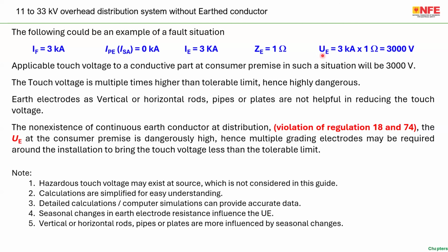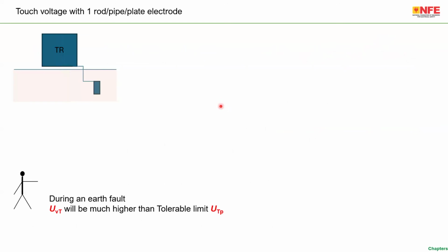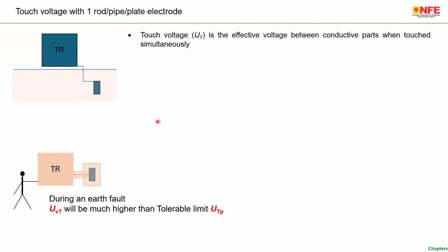So under this condition, without a metallic fault return path, or wherever you are violating regulation 18 and 74, the 11 kV side of the transformer will have a touch voltage much higher than the tolerable limit. Now I am showing you a transformer. Imagine this is an 11 kV by 400 volt transformer. The 11 kV is connected to one earth electrode, maybe a pipe or a plate. The top view looks something like this. There is a transformer, with a wire connected to the earth electrode.